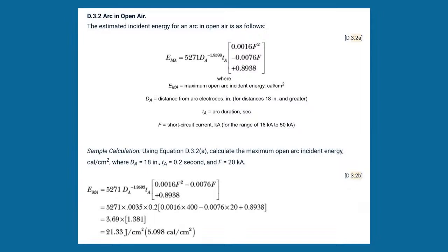It says, calculate the maximum open arc incident energy, and then we're going to tell you that the distance from the arc electrode is 18 inches, the clearing time is 0.2 seconds, and the short circuit current, or the available fault current, whatever you want to call it, is 20 kA. All right? Then all you're going to do is insert these values, and it's going to tell you that your cal rating for this arc is 5.098 cal. So now you know you have to put on at least, in this case, I'd say at least 6 cal. Absolutely. All right.